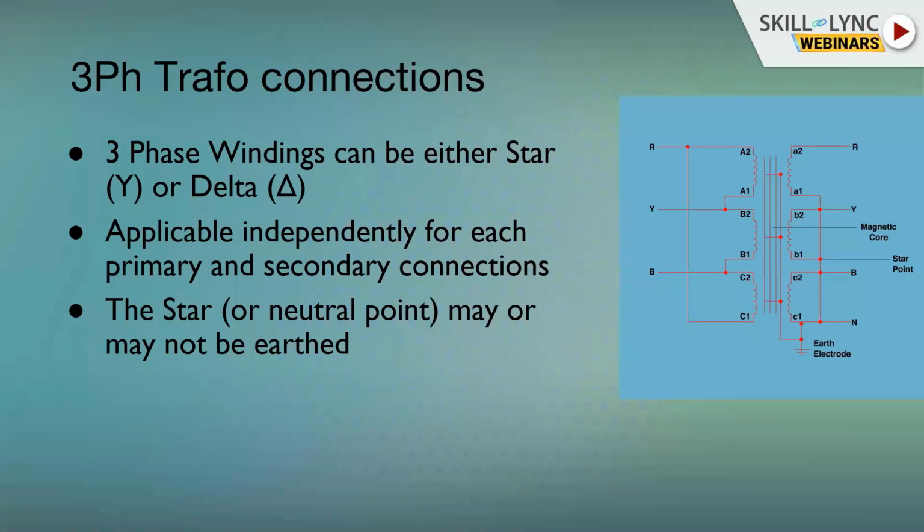As you all know, at the distribution level, typically in our cities and industries, when you're drawing power from, let's say, the ESCOMs, typically BESCOM or Tata Power, DDL in Delhi, the 11 kV side is typically connected in delta, and the load side is typically connected in star. And in case of a step-up transformer, delta is on the generator side, star is on the high voltage side. And we'll also talk about other types of transformers very shortly.